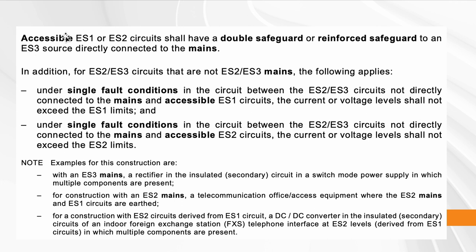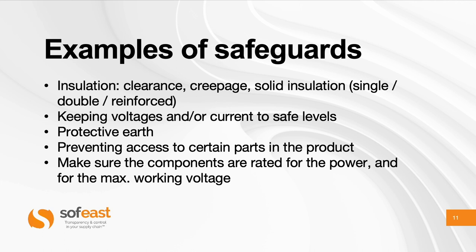This goes into a lot more detail — this is just a snapshot. For accessible circuits, meaning parts that don't require a special tool to access, you need a double or reinforced safeguard for an ES3 source directly connected to mains. You really need very serious safeguards that cover what happens under single fault conditions in different cases.